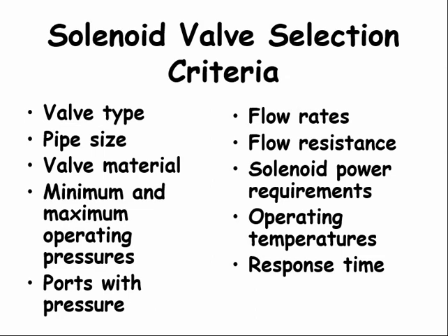Some valves require some pressure on all lines so that the valve returns to its de-energized state when de-energized. Flow rates and flow resistance values are important. The solenoid power requirements, duty cycle, and temperatures are things to consider too. And if timing or speed is important, what is the valve response time?